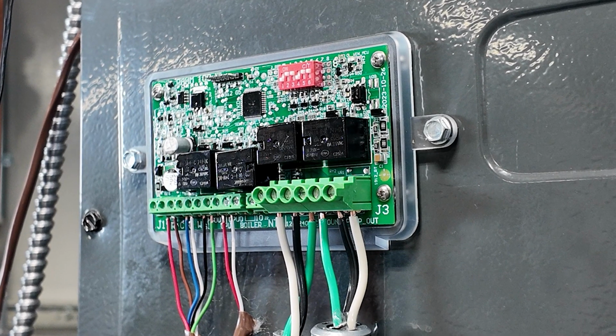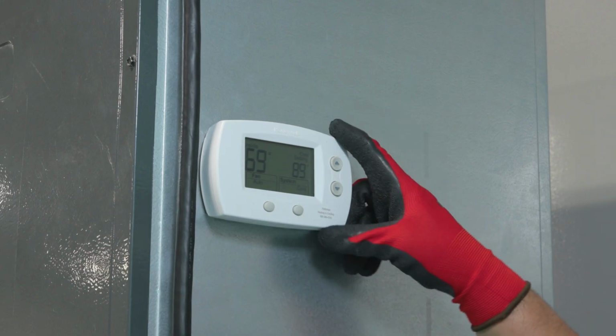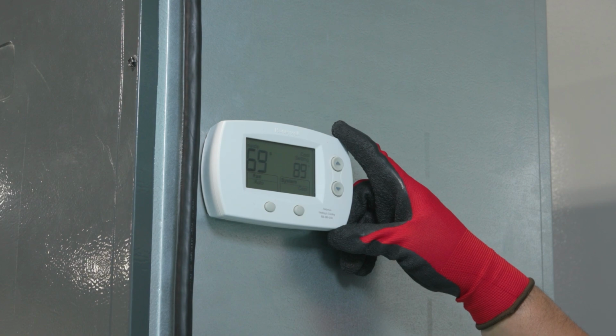And this is where the communication happens between the air handler thermostat and heating units like the Rinnai tankless water heater and/or boiler. Start with the low voltage lines. We'll go in order left to right. Remember, your thermostat should already be wired to the existing air handler.